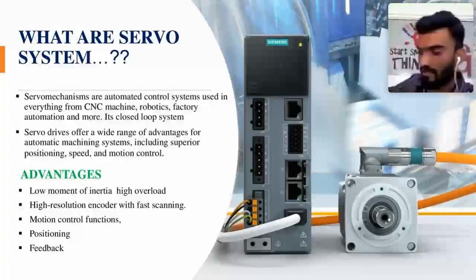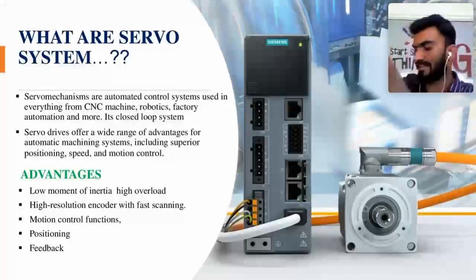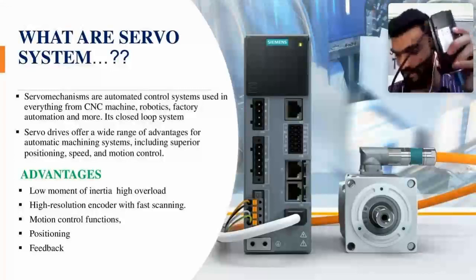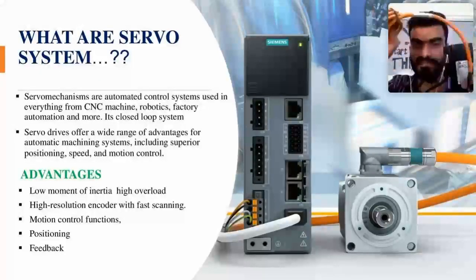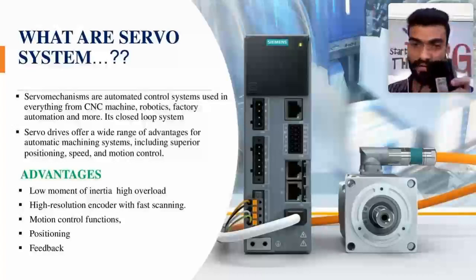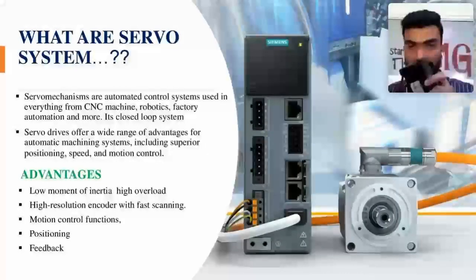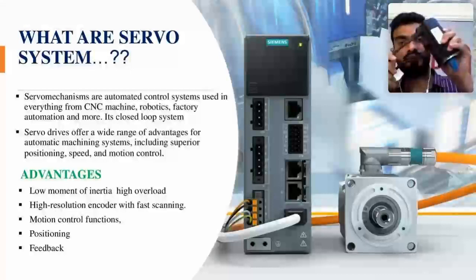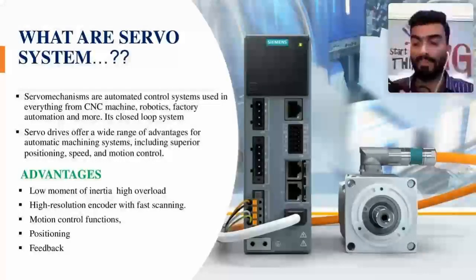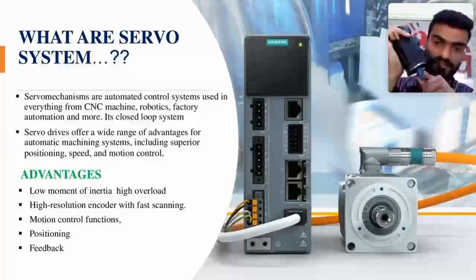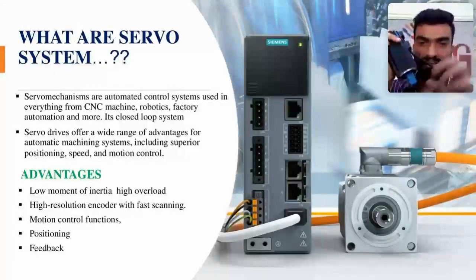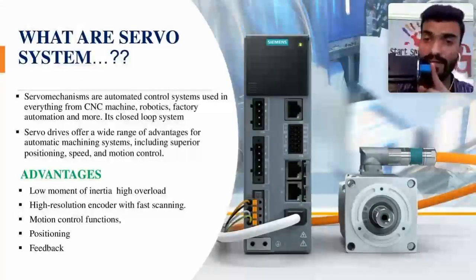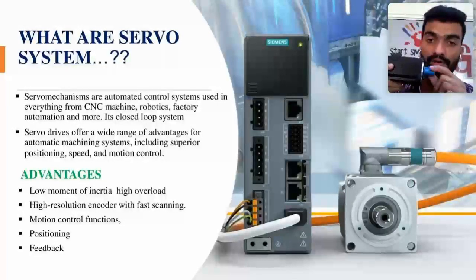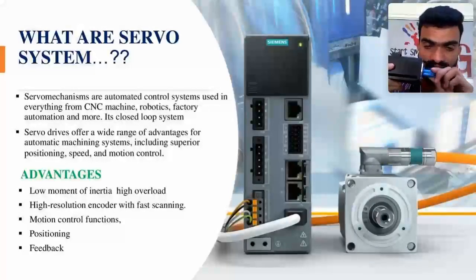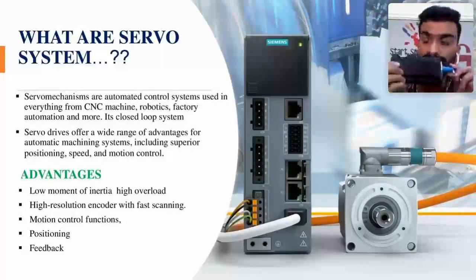The difference between an induction motor and this motor is that we'll be having two cables here. One is power and one is encoder. So this is a power cable, and there is one encoder cable. These two cables are given on this servo, because this servo is like a permanent magnet motor. The shaft runs between two permanent magnets. The accuracy of the servo will be more. These servos are used in CNCs and robots. All your robot arms are connected through this servo only. So this is a more compact and accurate one.